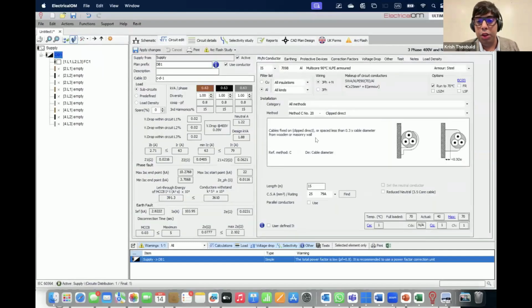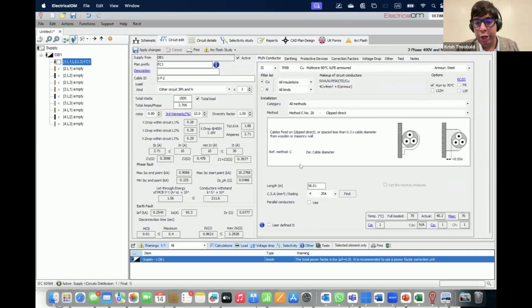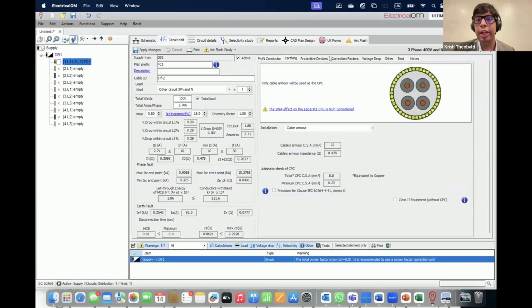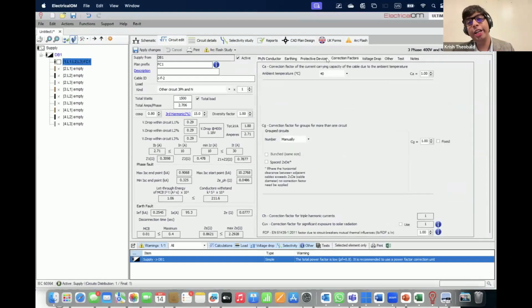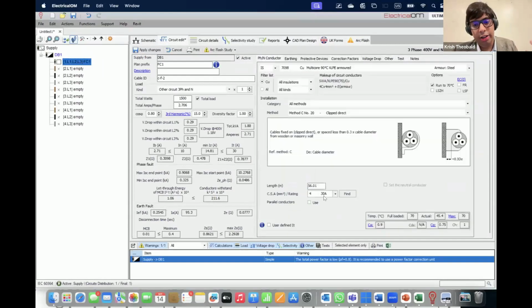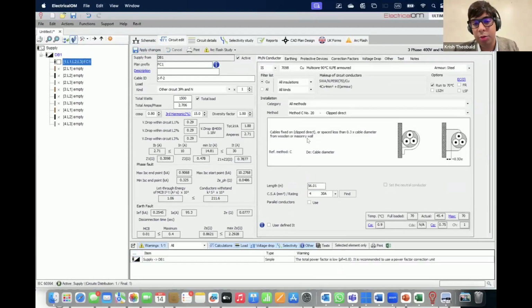Now, if I go to FC1, you see 56.01 meters is my length. So this affects my calculations for my earthing. It affects my calculations for the protective device, correction factors, everything. When we talk about correction factors, right? Say I've got 4 circuits next to each other, ambient temperature of 45 degrees. Well, it's not a problem in this case because our load current is relatively small as well. So yeah, that's how it works.